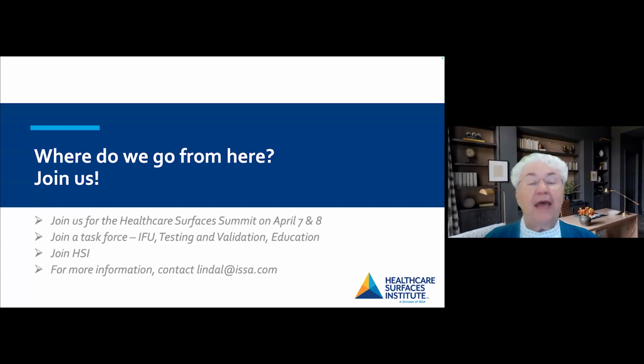Yeah, I'm going to take the last one. The Joint Commission says we cannot risk assess away the law, which are the IFUs. And we're not suggesting you do that. However, working with the manufacturer means they do more testing and they update their IFU. So that does become what you follow, not just I have an issue, so we're just going to try to risk it away.